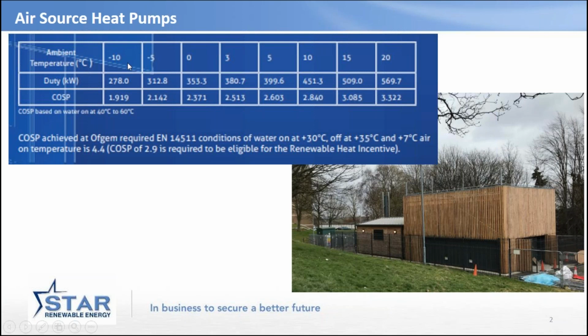You can see very clearly that the capability, the COSP, or the coefficient of system performance, varies. So if it's 20 degree ambient air temperature in Glasgow, frankly, you're probably not in Glasgow if it's 20 degrees, but the efficiency will be 3.3. If it's minus 10, which equally probably isn't Glasgow, it's about 1.9. Glasgow tends to range between 0 and 10. And so you can see the efficiency varies. The capacity varies as well, incidentally. So one of the downsides of air source is that the days that you want the most heat are the days when you have to work hardest to get it.